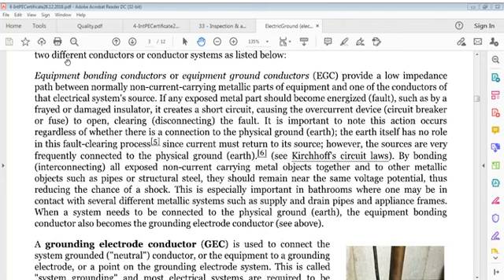It's important to note that this action occurs regardless of whether there is a connection to physical ground, that's earth. Earth itself has no role in this fault clearing process, since current must return to its source. However, sources are very frequently connected to physical ground, that's earth.